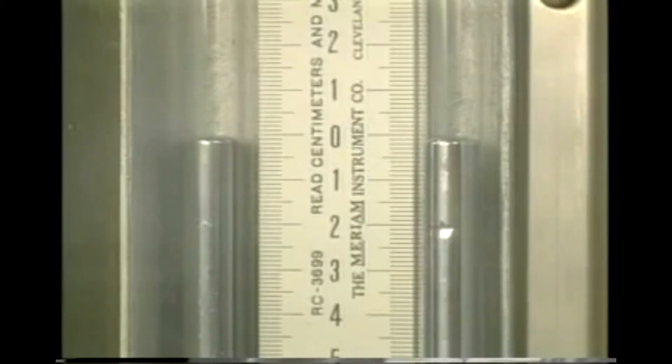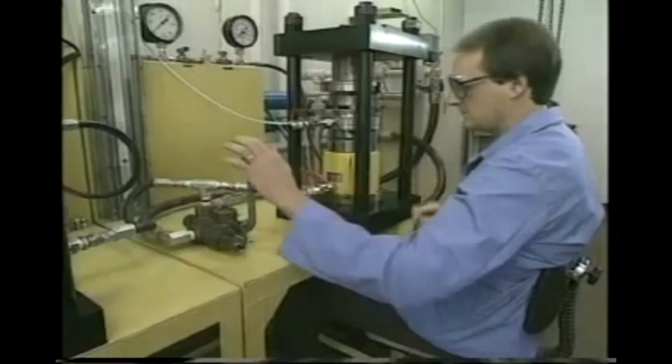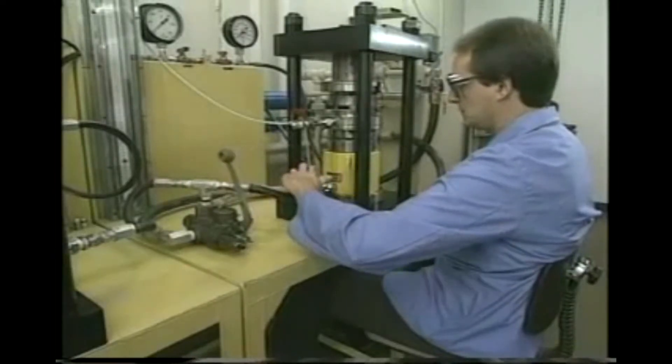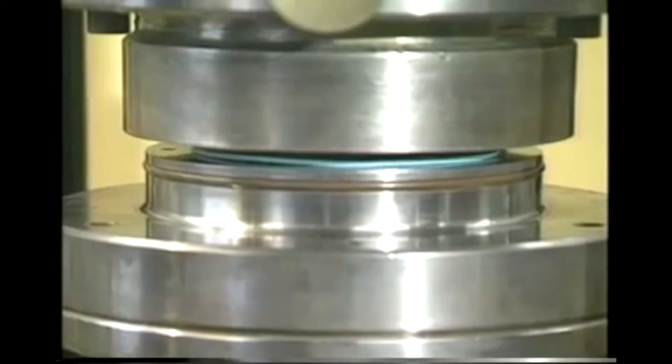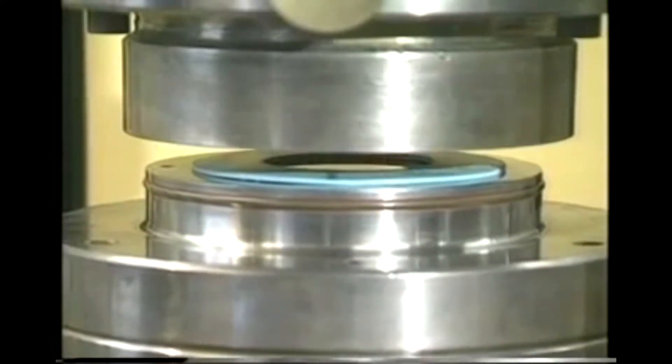This sophisticated equipment is designed to test products against the toughest European DIN standards. Similarly, leakage is indicated by a manometer, but this test is far more precise than ASTM F37, as it is hydraulically loaded, uses larger gaskets, and measures leakage only through the gasket.